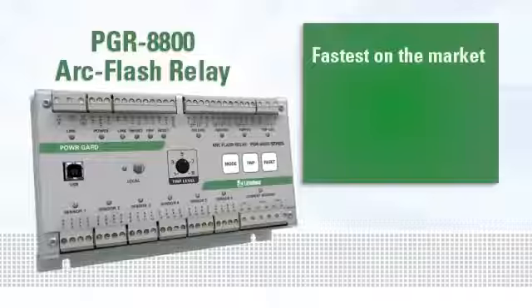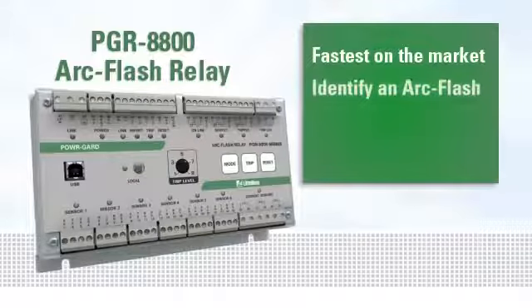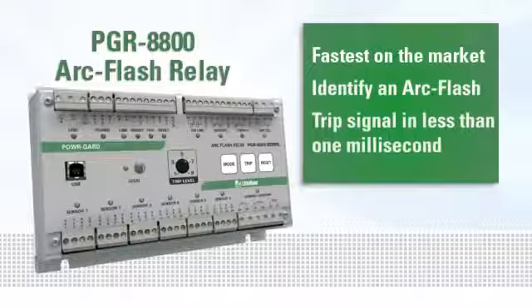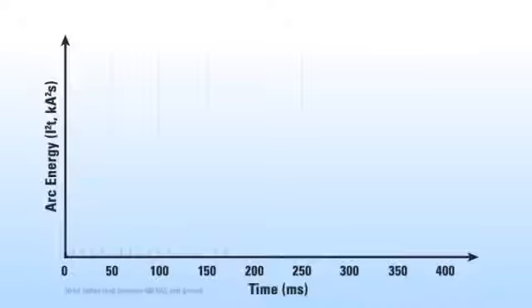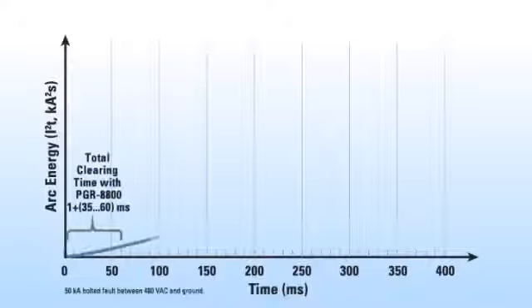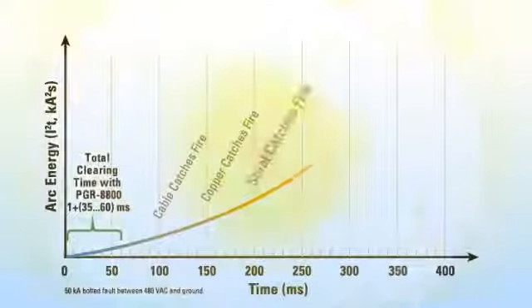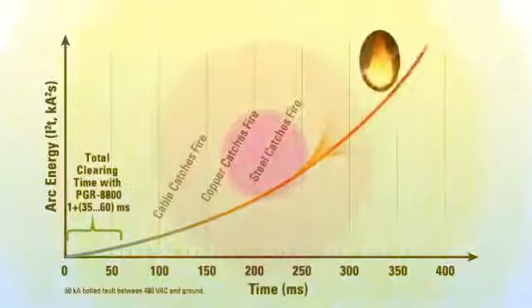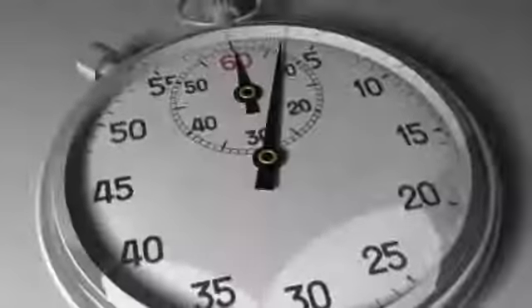The Littelfuse Arc-Flash Relay is one of the fastest on the market. It's able to identify an arc and send a trip signal in less than 1 millisecond. An Arc-Flash begins with a small spark. Now, as the electrical system continues to feed the spark, it grows in heat and intensity. In less than 1 second, the damages can multiply to a dangerous explosion and fire. That's why time is critical. Removing power quickly minimizes the released energy and the resulting damage.